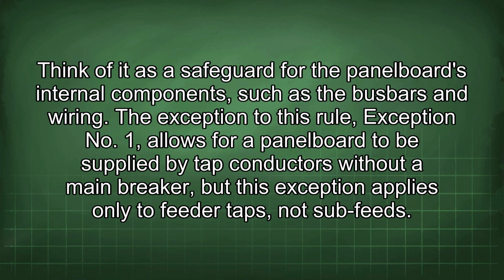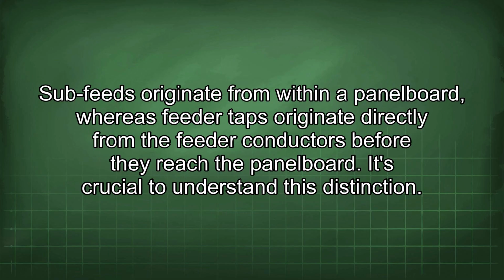Think of it as a safeguard for the panel board's internal components, such as the bus bars and wiring. The exception to this rule, Exception No. 1, allows for a panel board to be supplied by tap conductors without a main breaker, but this exception applies only to feeder taps, not sub-feeds. Sub-feeds originate from within a panel board, whereas feeder taps originate directly from the feeder conductors before they reach the panel board. It's crucial to understand this distinction.